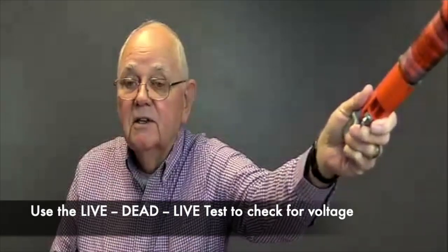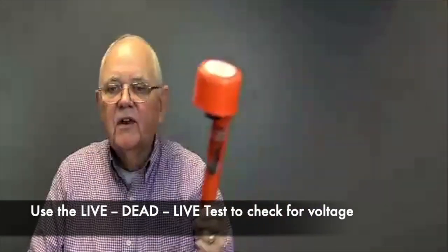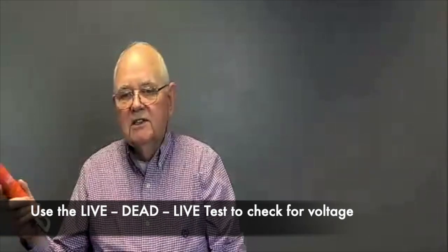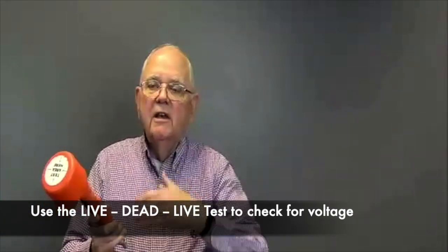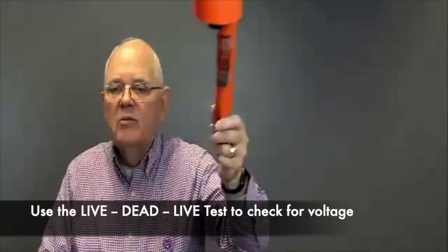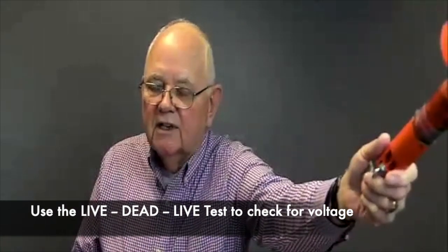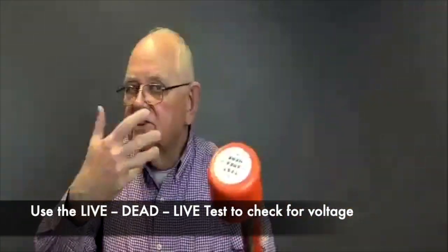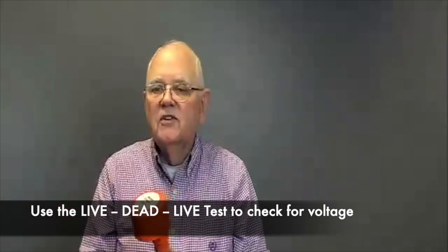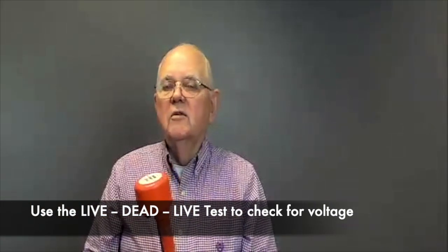Okay. So what I want to do is I want to take and put it up against a known source of voltage and make sure that it is working properly on voltage. Then I want to go in and test for the absence of voltage. And then, of course, the third point is I always come back and make sure that my voltage detector is still working properly. So it's still that 3-point live-dead-live test, even though I'm working at medium voltage.